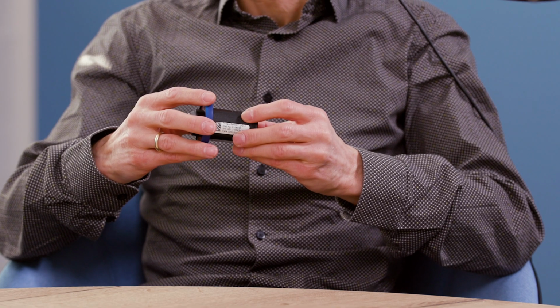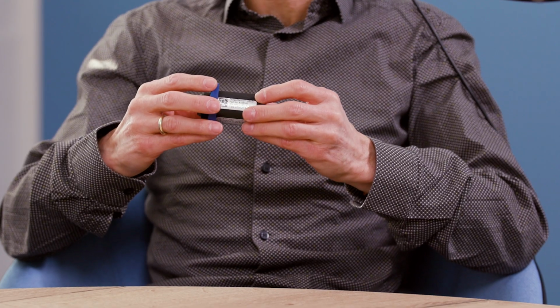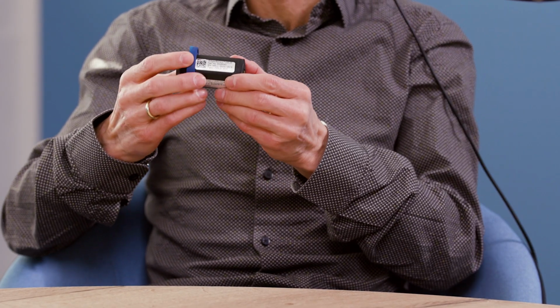Can you explain to me how the device actually works? Is it just very simply a microphone, or is there anything that we should consider? It's really easy. For the audible sound, we can use our ears, and we have a membrane in the ear which will convert the pressure fluctuations, the sound. It's like a microphone, the ear. Microphone membrane, and if we go to our ultrasonic gas leak detection, then we have this UGLD sensor, which is the same form as our electrochemical sensors.